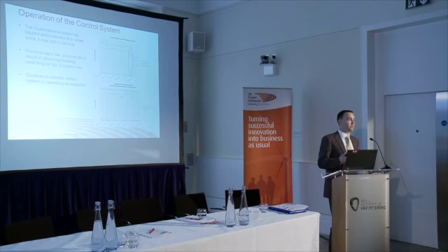So what we've done, obviously, to overcome that loss of data, if you like, that we don't have available, is to check the period between September and December, which is what we've analysed. We've ensured that we've analysed the Sudbury circuit to make sure there haven't been any significant step changes that would coincide with a deviation in the control system. And across the 3 months that we've analysed, the deviation never exceeds the upper or lower thresholds, and when it approaches that, it is tapped as it needed to.